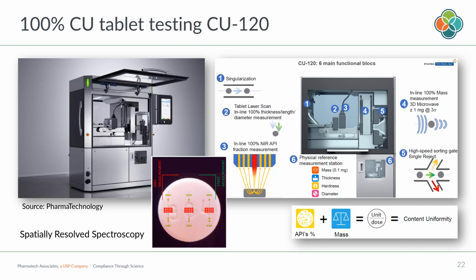So I think it's much easier in this case. But if you go to a low dose application, you might need another system. Here, a company, Pharma Technology, came up with another nice example. So that's a device with an SRS spectroscope where you not only get deeper into the tablet, but you can cover a wider range of the tablet. While this is fast enough to measure 120,000 tablets. So 100% basically, if you link this up to your compression machine.